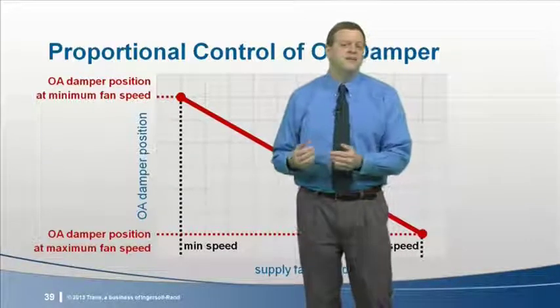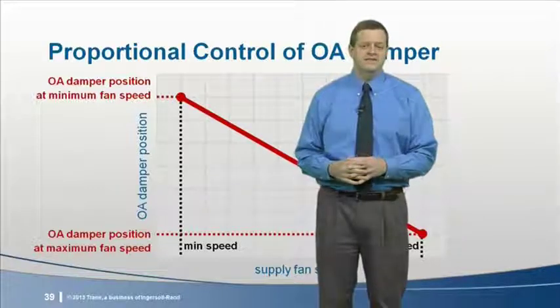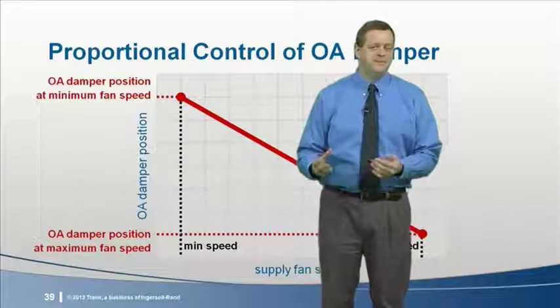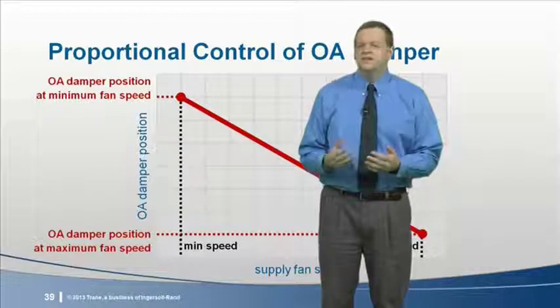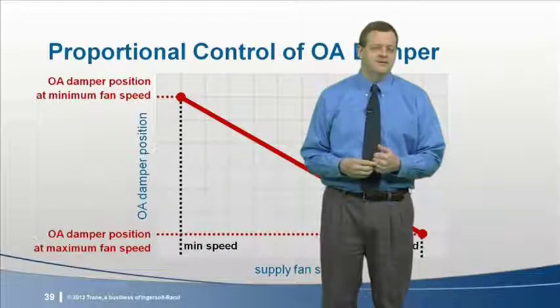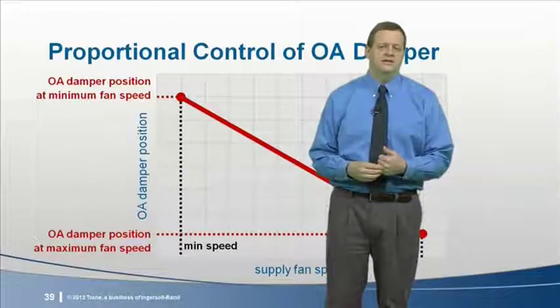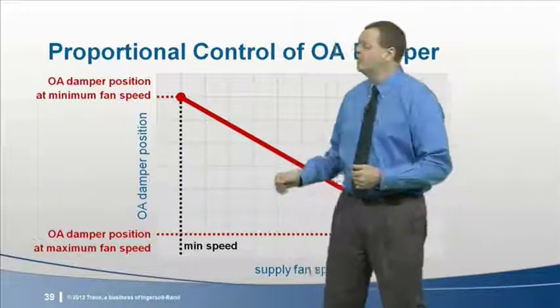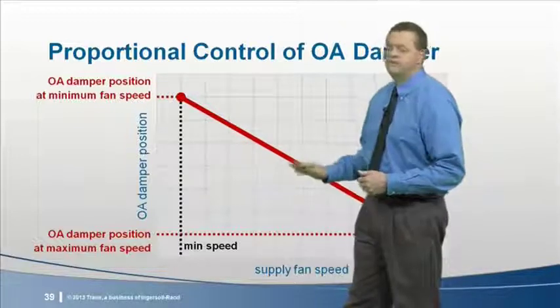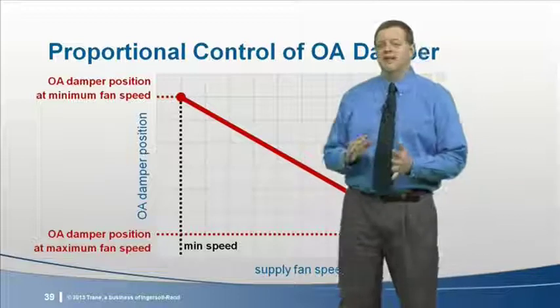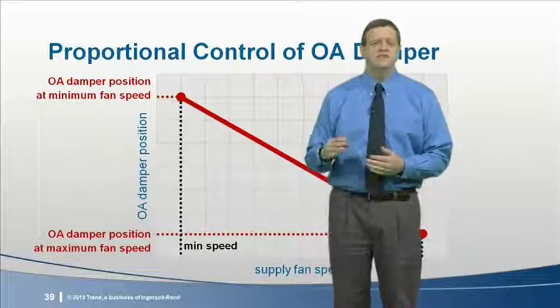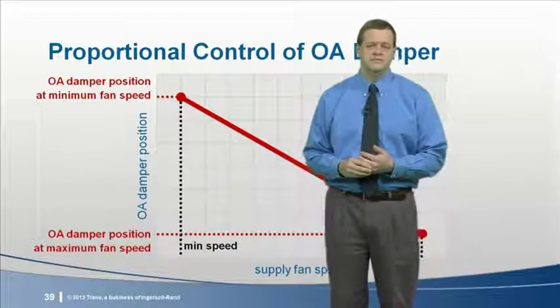Now, this method is not perfectly accurate over the entire range of airflows, since damper performance is nonlinear, and it doesn't account for outside influences like wind or stack effect. So it does result in some overventilation here in the middle of this range, but much less overventilation than if a fixed position damper was used.